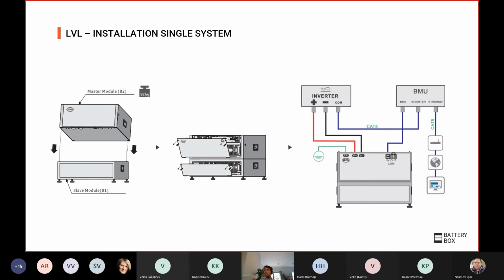The first step of the installation is quite simple. You just need to make sure that you put one module correctly on top of the other, and the connections will be made internally. You open the covers and connect the power connections and the communication connection on the right hand side. Just make sure that from the in of the BMS, it goes to the BMS port in the BMU, and from the inverter port you have the CAN cable. So we're putting Cat5 over there.